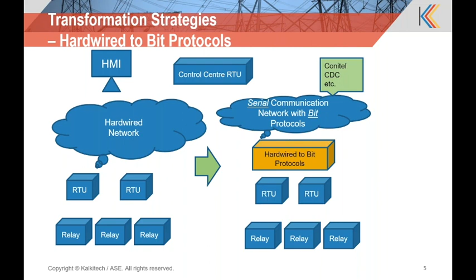Our other use case is converting from legacy bit to current byte protocols. Here we have a similar scenario with a Conitel CDC input to an RTU deployed in the field or substation, where the need is for serial communications with byte protocols. We presently have hardware only capable of bit-level protocols, so we provide that translation. We have an extensive protocol library, and our solutions can convert between bit and byte protocol formats—here we show Conitel data from the field being converted into DNP3 byte stream data.